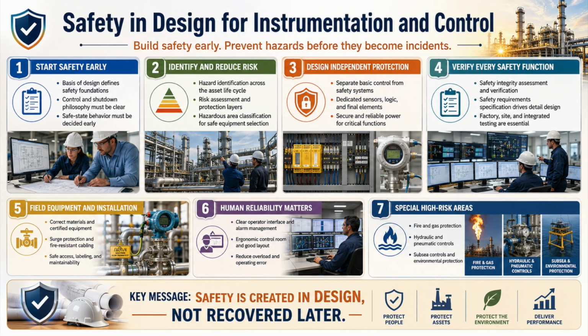Field equipment must be selected for the actual environment, not the catalog environment. Consider temperature, sunlight, chemicals, corrosion, marine exposure, fungi, rodents, vibration, flooding, dust, and mechanical damage. Materials must resist both the surrounding atmosphere and the process fluid. Hydrogen sulfide, carbon dioxide, chlorides, and contaminated surfaces demand coordinated material review across instrumentation, piping, process, and metallurgy. Lightning and electrical surge protection must prevent field disturbances from propagating into control and safeguarding systems. Critical instruments require suitable grounding, local surge protection, and coordinated protection at equipment rooms.